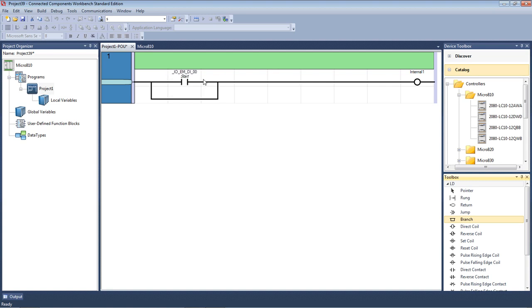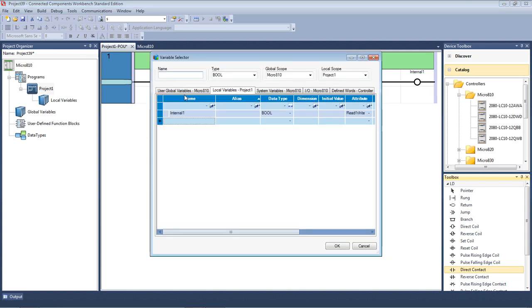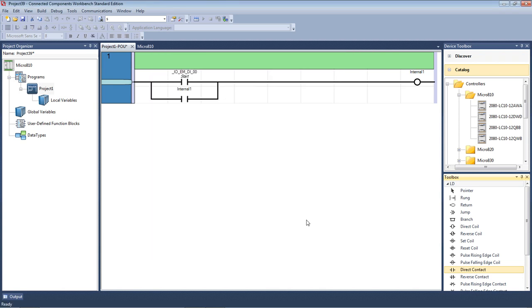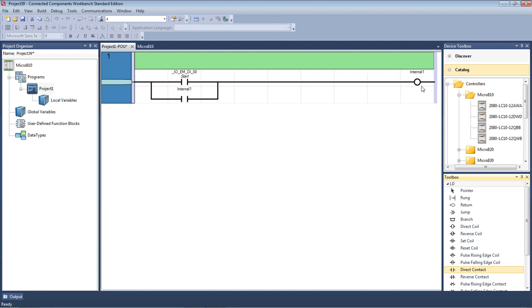So I'll bring my direct contact over, drag a direct contact over, drop it in. And I'm going to use my internal one, so I'm going to use the internal one internal relay here. So what that is, it's a contact off that internal relay. So it acts exactly the same in, as far as your logic goes, it acts exactly the same as it would do with an external relay output. But again, like I said before, it's so we don't waste our external relay outputs, because we only have four of them.